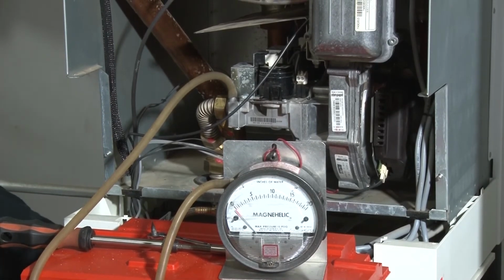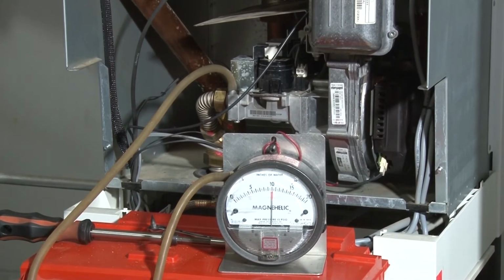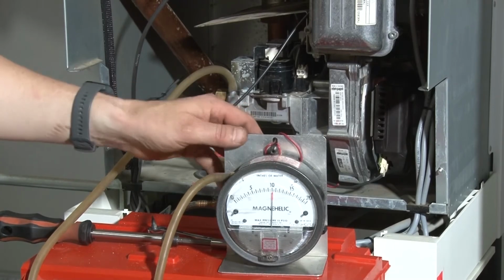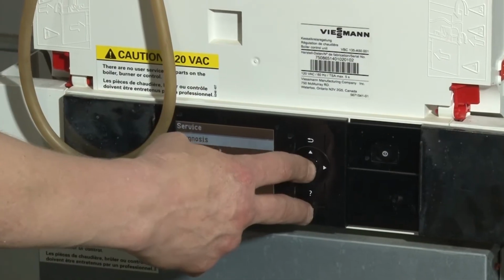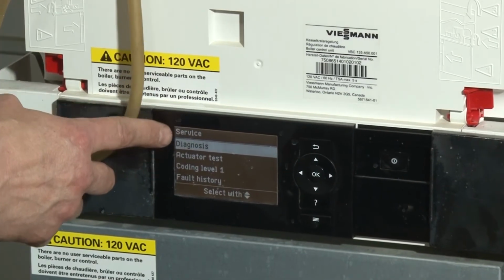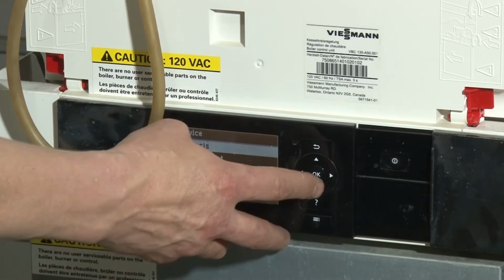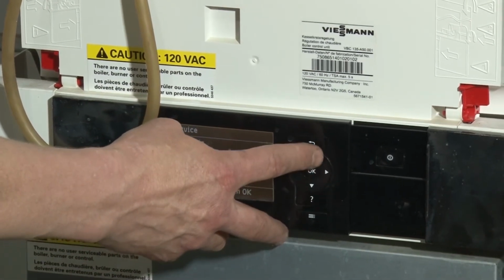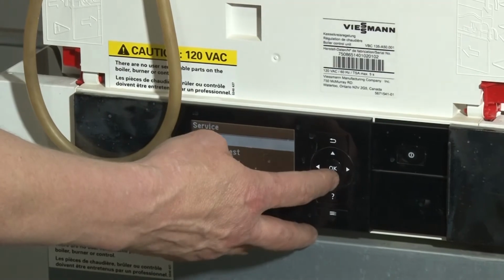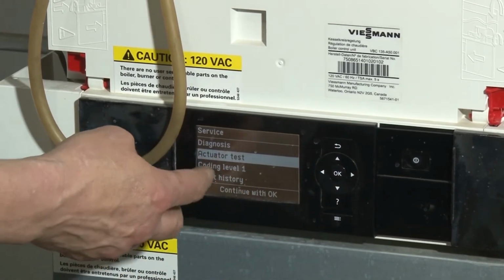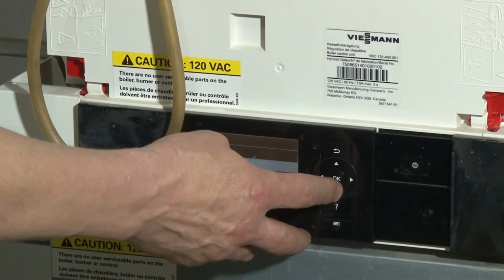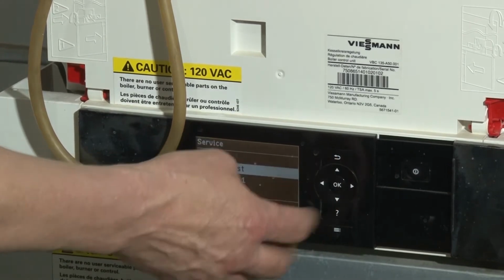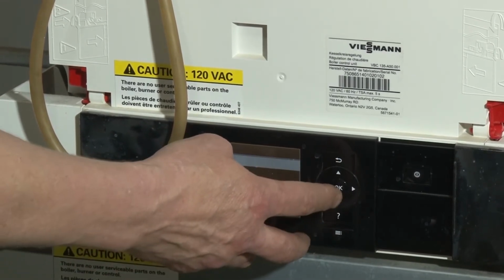Otherwise, we have to make some adjustments in our rig. So we'll turn the gas back on, and we check our pressure here, and that puts the screen into service. And as I go down here, you have a bunch of different areas here that you can kind of check out. Diagnosis is a really cool one for troubleshooting. Actuator test is what I'm going to want to get into here. You've got fault history. I can see what all the different faults this boiler had. They're going to give me information on if there's any issues.